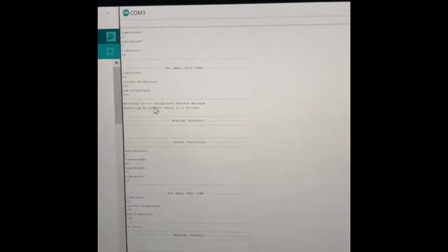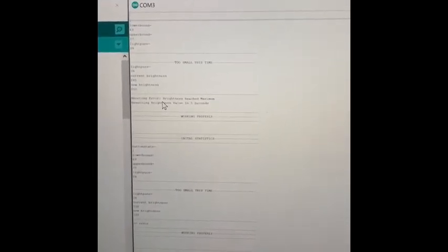It went back to 150 right here. There you go. And that was after the error code that came up. I'll actually turn off auto scroll for 2 seconds so I can go back to that, because that's a cool thing I wanted to point out. Basically right here, it pops up the error code after it reaches 250, which is 5 off of the maximum. And I feel like I could make it the maximum.